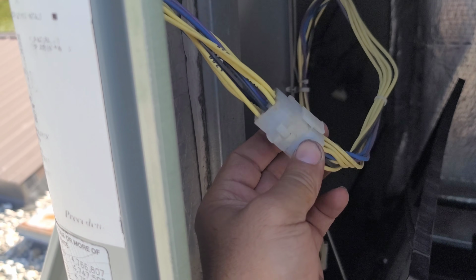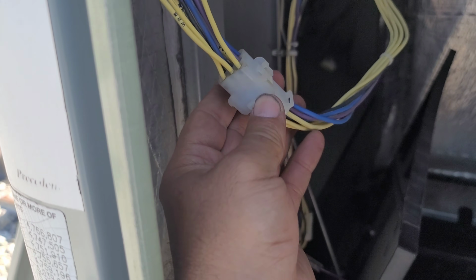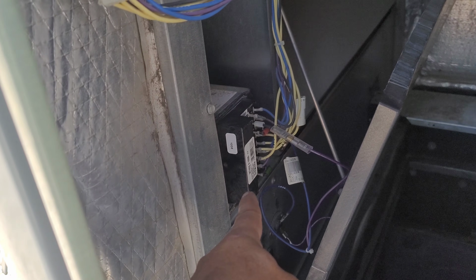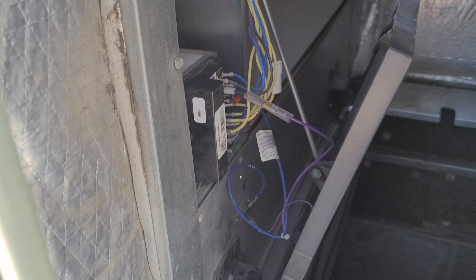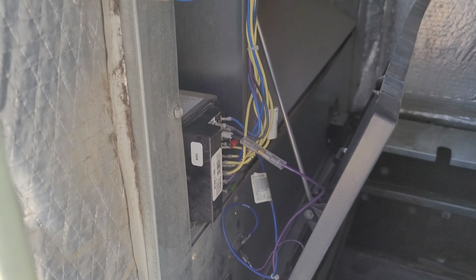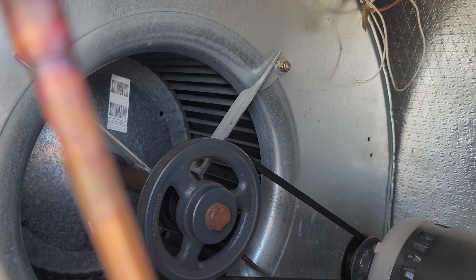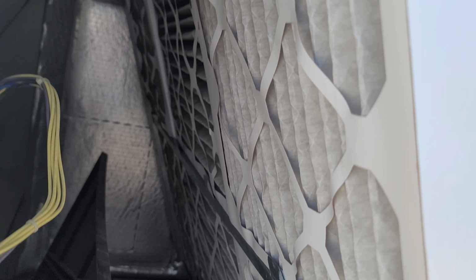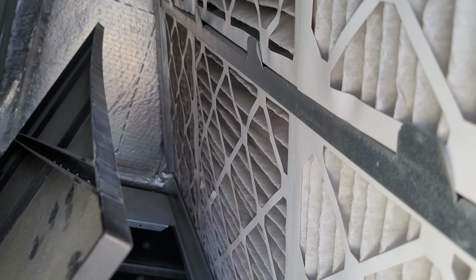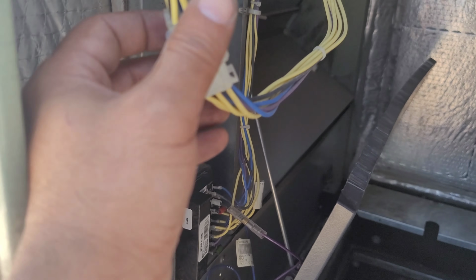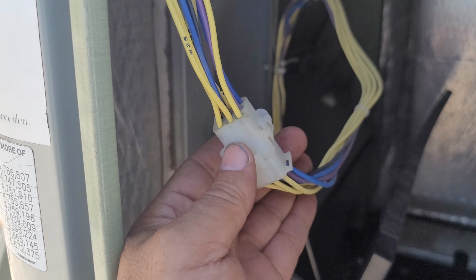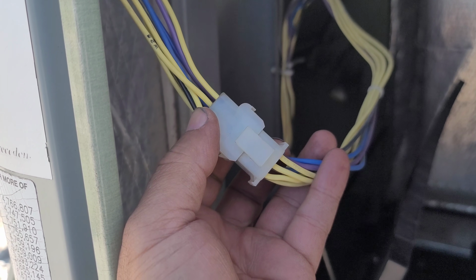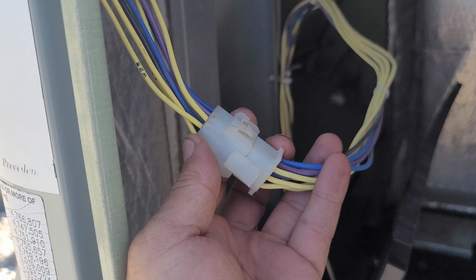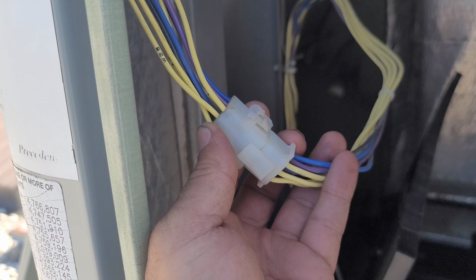Okay, so this is the plug we saw in the wiring diagram, and this is the economizer board here. All the wire looks connected, everything is looking nice and tight, but our AC is not working, so I have turned off the power. This is the blower, the belt is nice and tight, so we're gonna replace the filter. Filter looks a little bit dirty but not critical, plugged up. So now the next thing, we're gonna remove this plug, and so we will bypass as per the wiring diagram Y1 and Y2, and we'll see what happens.